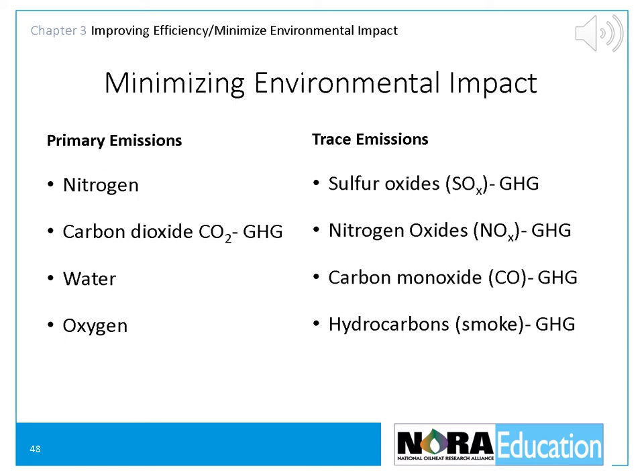The next emissions are sulfur oxide emissions. Research by the U.S. Department of Energy at Brookhaven National Lab, the Canadian CET, and others has shown a direct relationship between the sulfur content of home heating oil and the fouling deposits built up on heat transfer surfaces. As the percentage of sulfur in the fuel is reduced, the rate of heat exchanger fouling drops, and the need for vacuum cleaning decreases. Research in Germany indicates that the use of ultra-low sulfur fuel improves efficiency by over 1% to 2%.